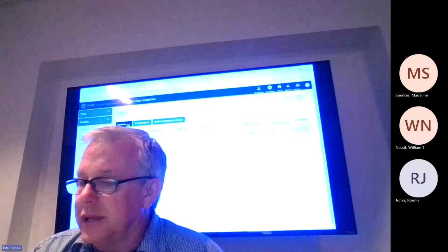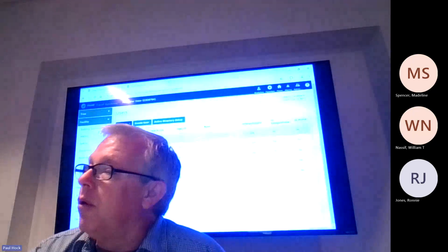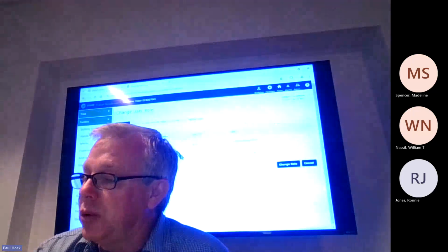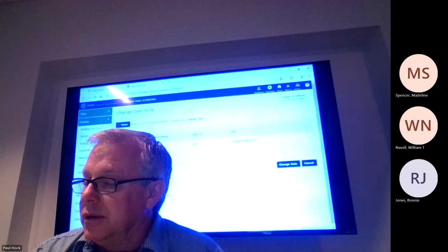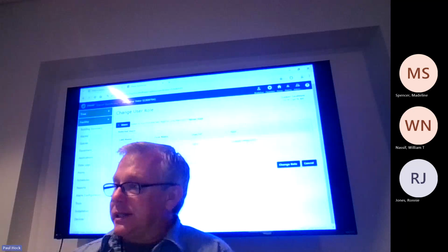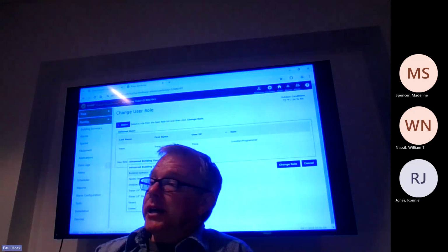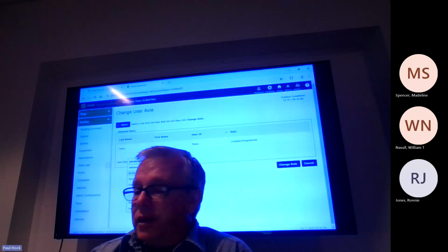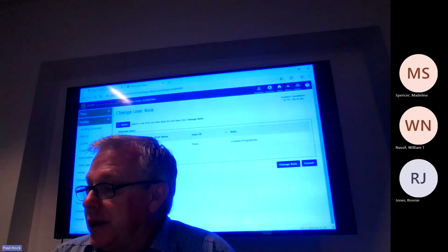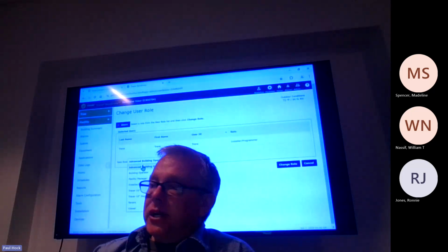Actions. We'll say I can change the role. Okay, so there's a few roles that you can do. Installer programmer is full access. You can just do a basic building operator where they can go in and change set points. You can do advanced building operator where they can do set points, alarms, set up alarms, change schedules, stuff like that.